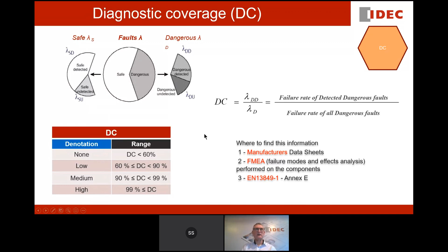So we need to calculate the diagnostic coverage or the DC average. And if you remember, going back, everything is broken down into the individual elements that make up your safety channel. So for your first device, you take your diagnostic coverage that you've looked up in your data sheet, you divide it by the MTTFD that you've calculated from your number of operations per day, and then you divide all of that by the reciprocal of the MTTFD for that device. So it's device 1 plus device 2 plus device 3 up to device infinity.